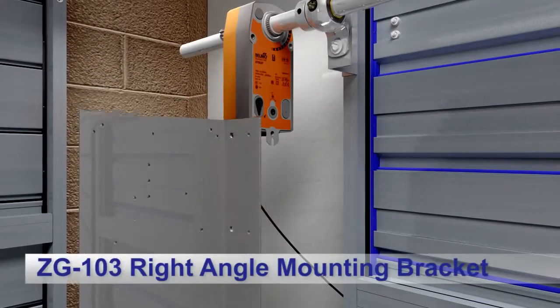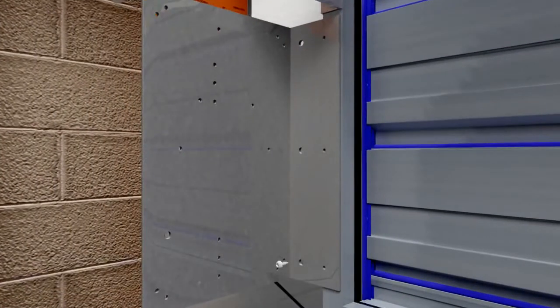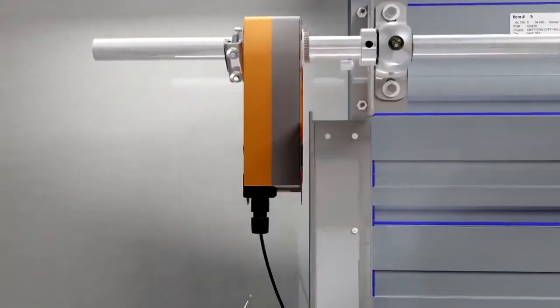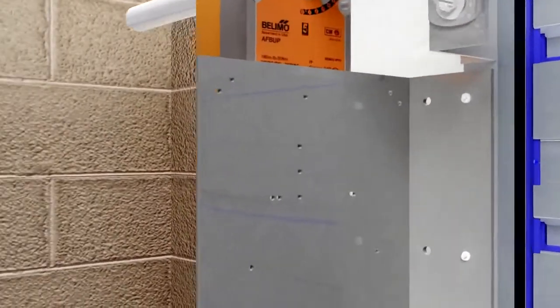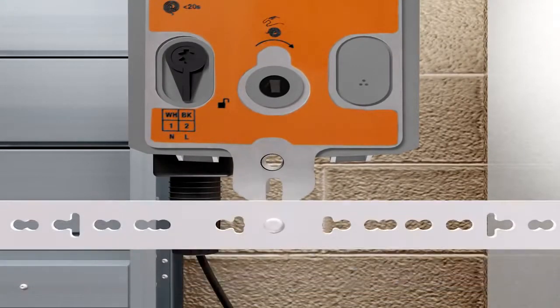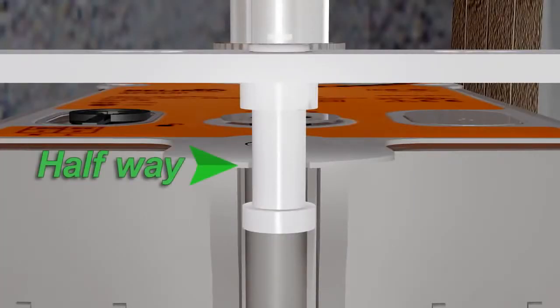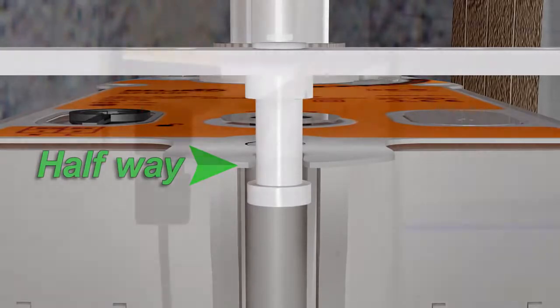Attach a Belimo ZG-103 right-angle mounting bracket to the damper frame with self-tapping screws. The mounting bracket should be set at the proper height so that when the anti-rotation bracket is attached, the U-shaped slot at the base of the actuator plate will fit over the stud of the anti-rotation strap. The stud should be positioned approximately halfway up the U-shaped slot.